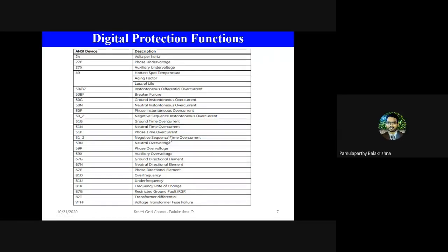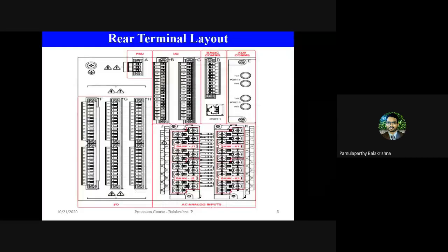Thanks for asking that. So when we look at the backside of the digital relay, this is the backside of a digital relay. One of the unique features this digital relay offers is modularity in design. What that means is, as I said in my previous slide, the relay receives various inputs like current from CT, voltage from PT, digital input, analog input, digital output, analog output, and various communication and time synchronization. At any point of time, at any location in any substation, it may not be possible to use all the available components in the relay.